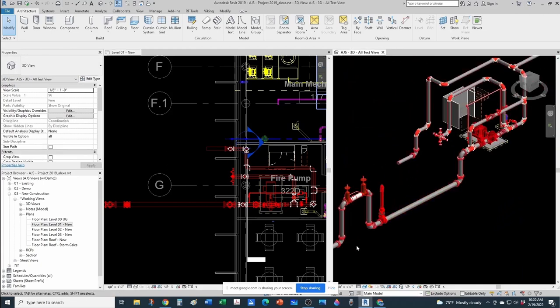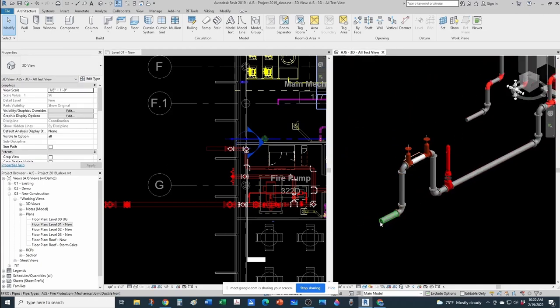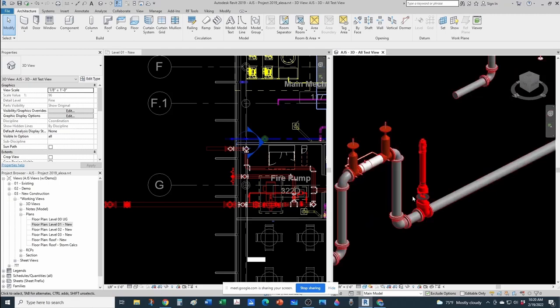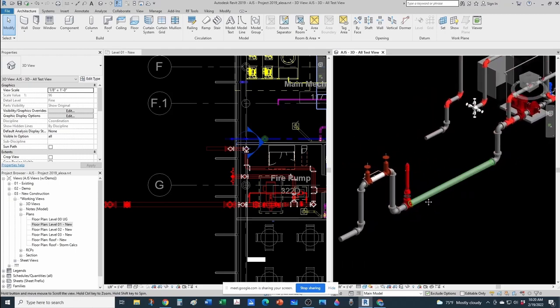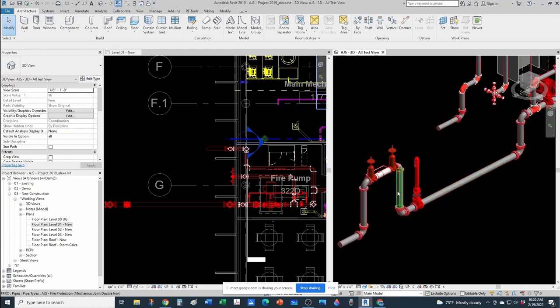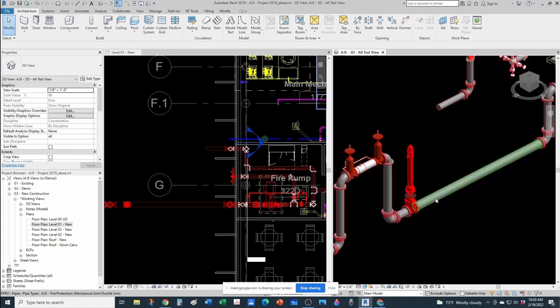So, let's do a quick overview of what we want. Again, this is the suction from the city, that backflow preventer, that post indicating valve. In some buildings, you will see a backflow preventer, post indicating valve, and then a fire department connection right after it. And that would be attached to that suction line.